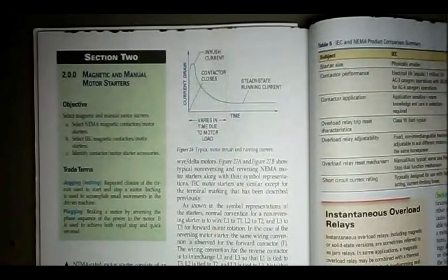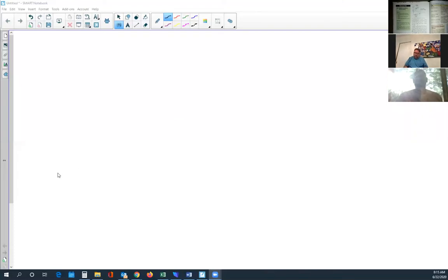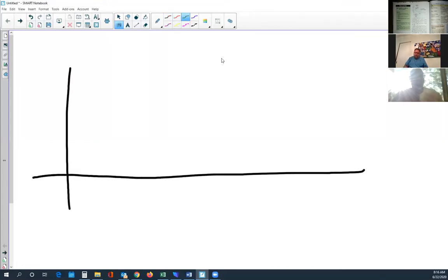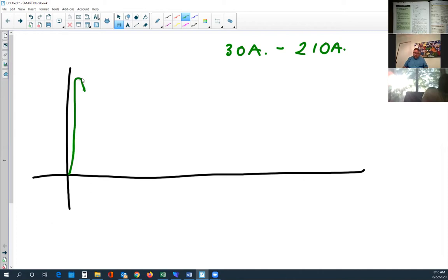Now I'm going to share my screen with you. And hopefully I still have my sound, but there. If the run current for a motor is 30 amps, the start current can be 210 amps. It can be 7 times that, 700%. When you start the motor, this start current very quickly, that's supposed to be almost vertical, rises to that 210 amps. And then as the motor turns, this current will come down to the running current of 30 amps.